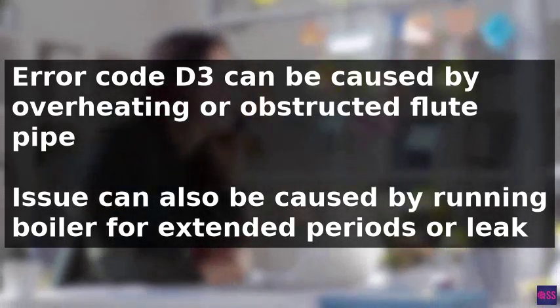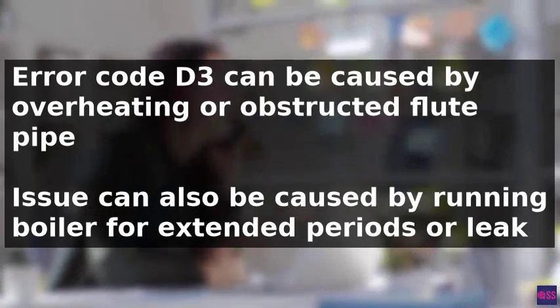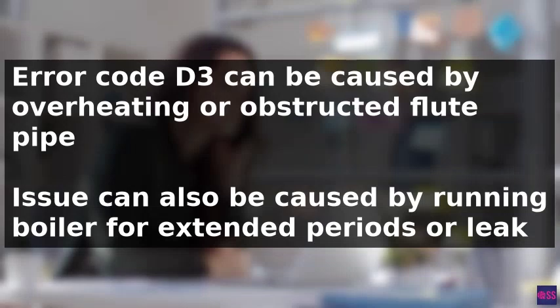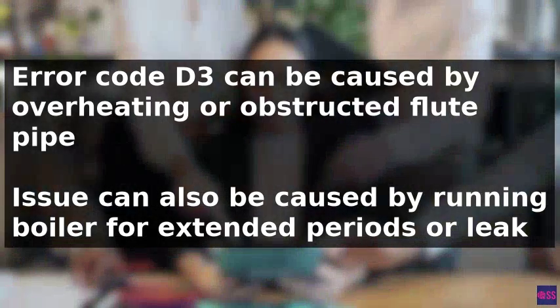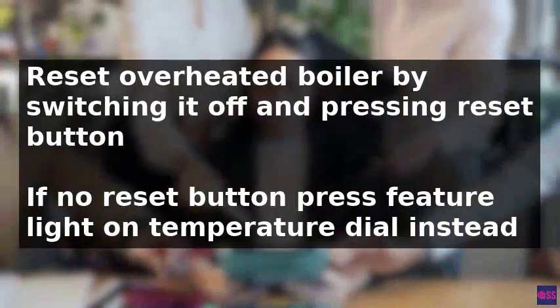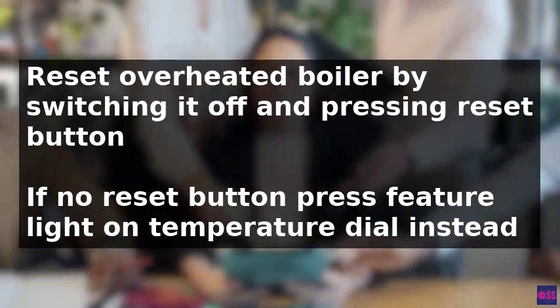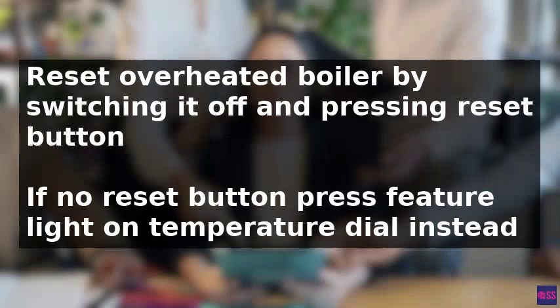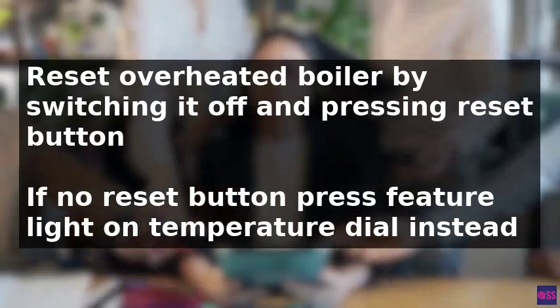To resolve the error, it is necessary to reset the overheated boiler by switching it off, then pressing the reset button for at least 5 seconds. If the boiler does not have a reset button, the feature light on the temperature dial can be used instead. Press the reset light for at least 5 seconds and check if the boiler has started functioning again.